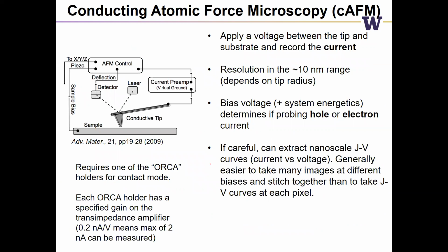So I'll march you through some of the different techniques that are available. The first and most basic one for electrical AFM is conducting atomic force microscopy. Here you're applying a bias between your tip and your sample, and then measuring the current. It's very simple. The tip has to be in contact mode in order for you to get current, and the tip has to be connected to a current preamp that's built into the chip holder, so you don't have to worry about building that. The resolution is in the 10 nanometer range, depending on the tip radius.